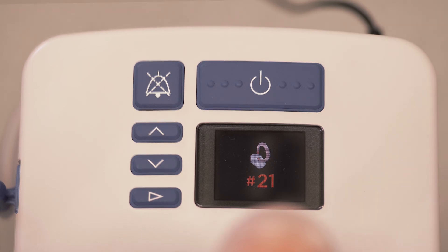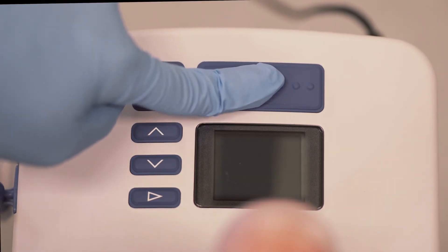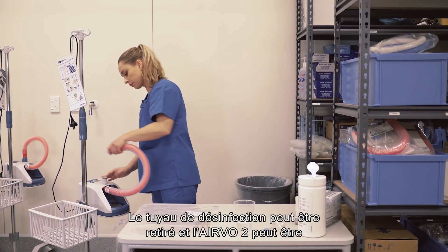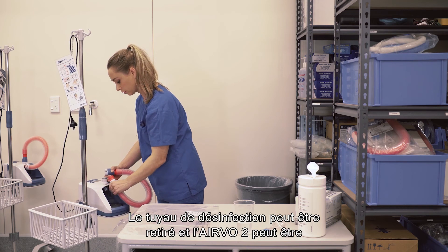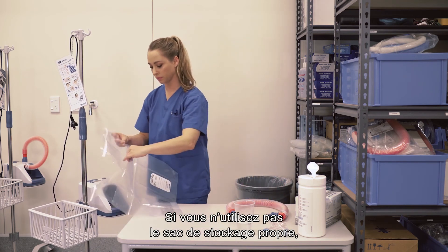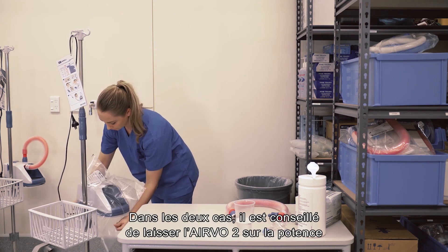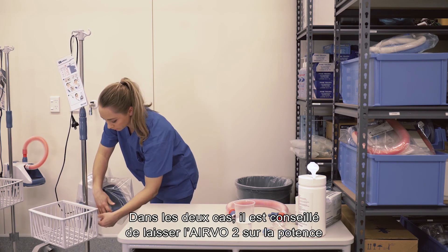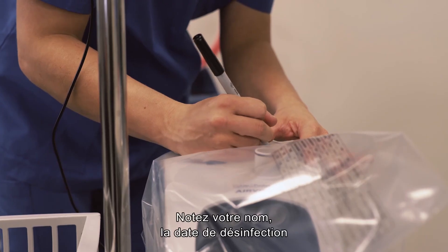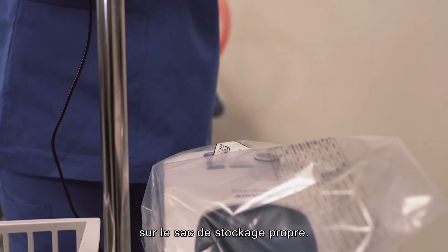Finally, turn the AIRVO 2 off by holding down the power button. Disinfection is complete. You can remove the disinfection tube at this stage and seal the AIRVO 2 with a clean storage cover. If you are not using the clean storage cover, you may prefer to leave the disinfection tube in place for storage. In either case, it is best to leave the AIRVO 2 on the stand to protect it from bumps and knocks. Write your name, the disinfection date and the disinfection number on the space provided on the clean storage cover.